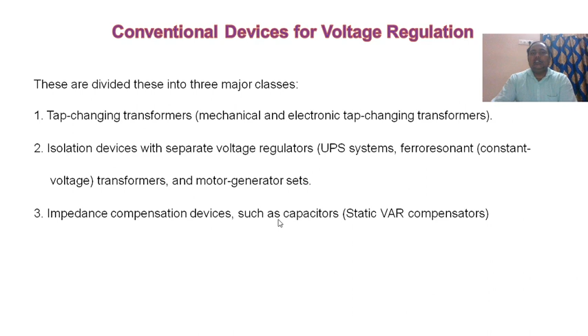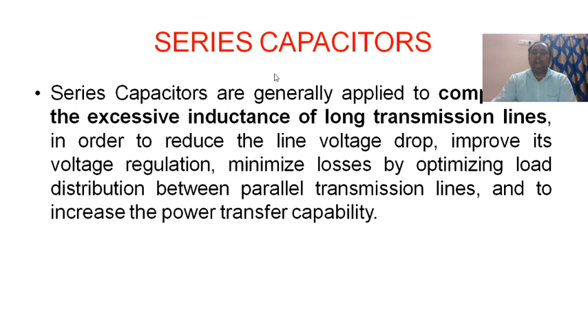What are series capacitors? Series capacitors are generally applied to compensate the excessive inductance of long transmission lines, in order to reduce the line voltage drop, improve voltage regulation, minimize losses by optimizing load distribution between parallel transmission lines, and to increase the power transfer capability. For increasing power transfer capability, we must use series capacitors.